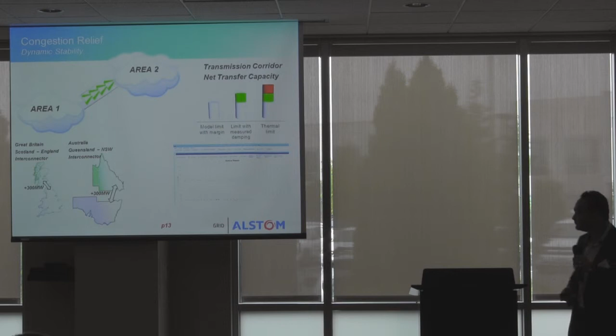What we've done in the UK and in Australia is use it to relieve congestion across corridors. In both cases, coincidentally, we've tapped into about 300 megawatts of latent capacity across those corridors. That's because we've combined measurement-based solutions and model-based solutions. With the measurements, we've been able to quantify the amount of conservatism in the planning studies and actually push the edge of that limit.